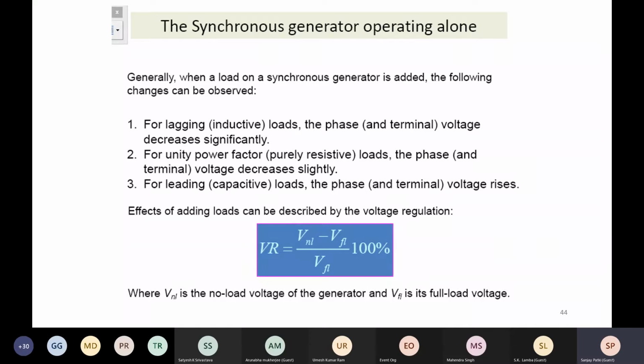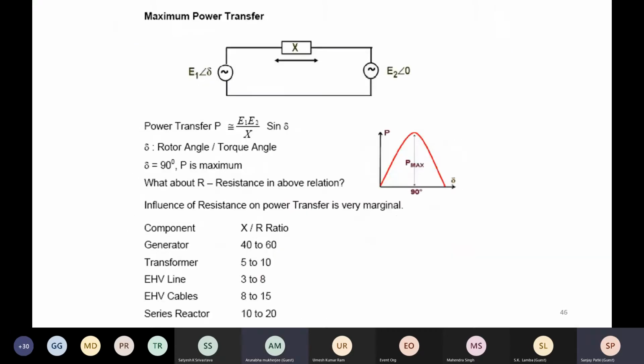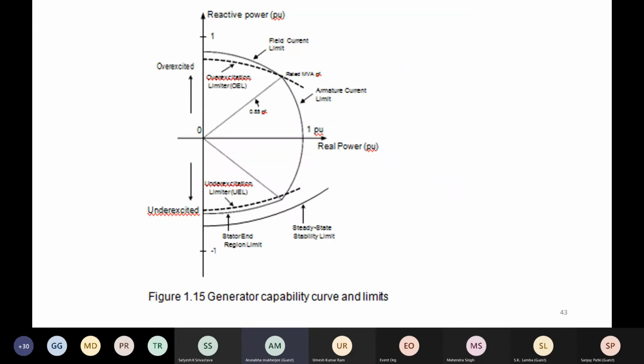So we discussed this regarding the lagging, unity, and leading power factor and its effect on the regulation. Sir, one question on that particular point. Suppose our machine is running at full megawatt, and suppose the grid is asking for more MVAR. This is our prime responsibility, to support the grid, sir. In that case, how much will we support, or will we immediately contact the RLDC, that our machine is being asked for high MVAR, the grid is asking for high MVAR, so please regulate it?